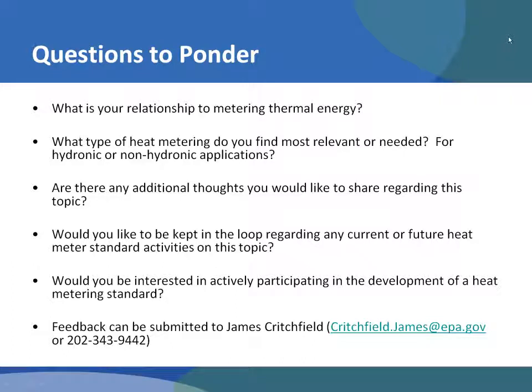So Daniel also asked, why isn't a condensate meter considered? It can be. A lot of times you don't get all the condensate back. It's trapped out in different parts of the system, and so that part of it is a little tough. We have a lot of customers that measure both the steam output and the condensate, as well as the boiler feed into the boiler, in an effort to see exactly what's going on with the system. That way, number one, you've got a self-checking instrumentation system, and number two, you've got the capability of finding out things that are happening in your system that you may not be able to catch otherwise.